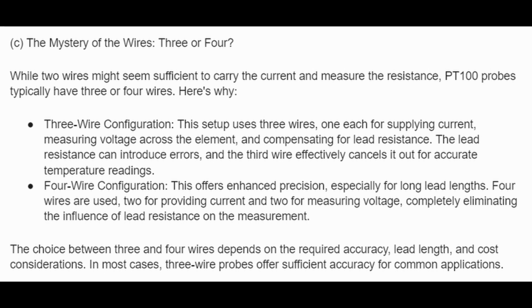4-wire configuration. This offers enhanced precision, especially for long lead lengths. 4 wires are used, 2 for providing current and 2 for measuring voltage, completely eliminating the influence of lead resistance on the measurement. The choice between 3 and 4 wires depends on the required accuracy, lead length, and cost considerations. In most cases, 3-wire probes offer sufficient accuracy for common applications.